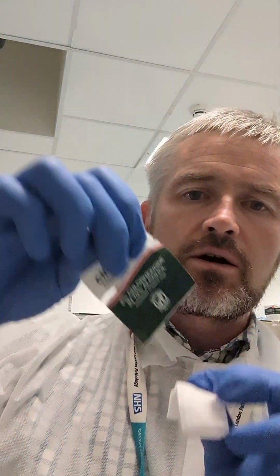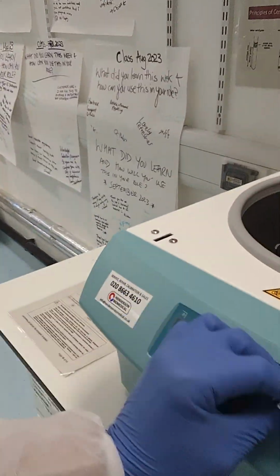In preparation for this, I have actually opened some before. So these are the 70% alcohol wipes that we're using. We remove the buckets. You can wipe the outside of the buckets, handles, and you can even get the wipes into the actual sample containers. Use multiple wipes to then clean the outside of the buckets, clean the inside of the buckets, and also to clean the drum and check for debris while you're doing it. Then use further wipes to wipe down the areas that you touch on the front of the instrument and the lid.